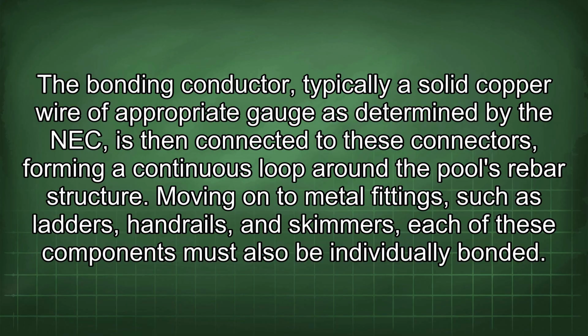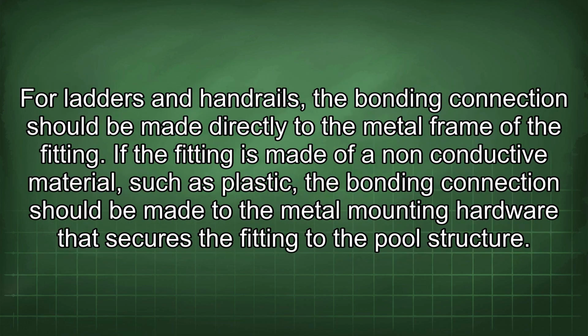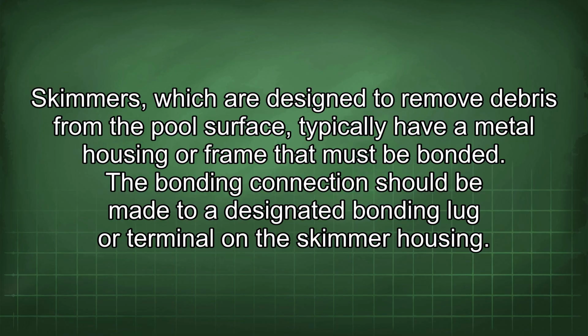Moving on to metal fittings such as ladders, handrails, and skimmers, each of these components must also be individually bonded. For ladders and handrails, the bonding connection should be made directly to the metal frame of the fitting. If the fitting is made of a non-conductive material, such as plastic, the bonding connection should be made to the metal mounting hardware that secures the fitting to the pool structure. Skimmers, which are designed to remove debris from the pool surface, typically have a metal housing or frame that must be bonded. The bonding connection should be made to a designated bonding lug or terminal on the skimmer housing.